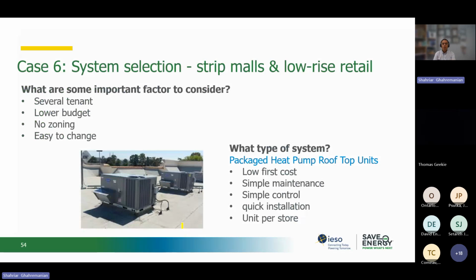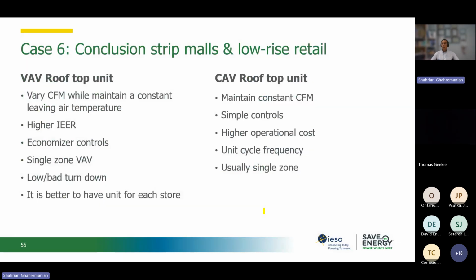The other example that I have is for a strip mall or a low-rise retail building. In these cases, we have several tenants, typically a lower budget, and sometimes we don't want to do zoning. So each tenant wants to have only one unit that is easy to change, because for each tenant we just remove the rooftop unit and install a packaged heat pump. So the first cost will be lower, the maintenance becomes simpler, and the control also becomes simple, with quick installation and one unit per store. That's a good option to be considered.